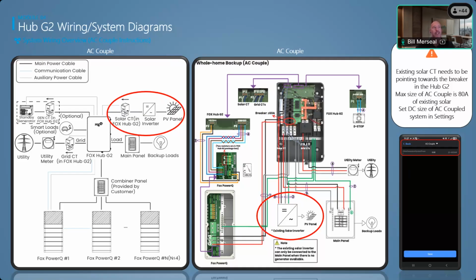If you leave that in-phase breaker in the main panel without switching it over to the hub, we don't have the ability to shut down that solar system. So when the power goes out, your solar system will also go out — it's not going to island, because the only way your solar system would work during a power outage is if there's power to those inverters.